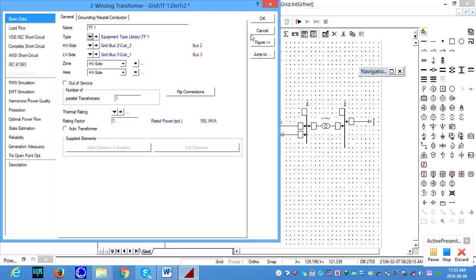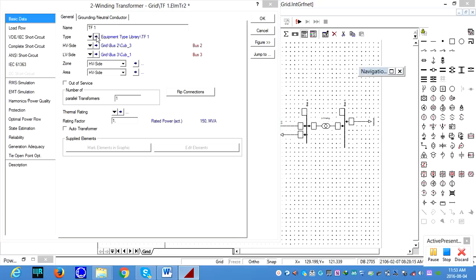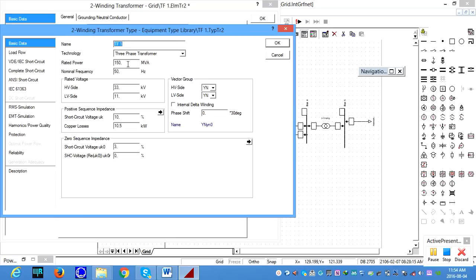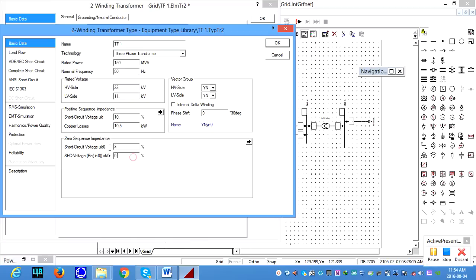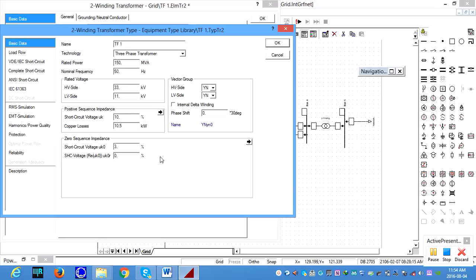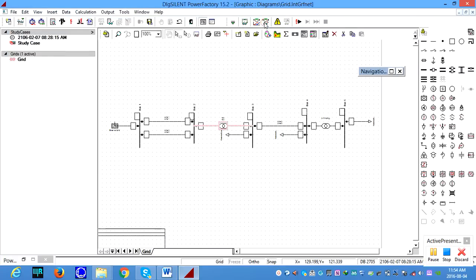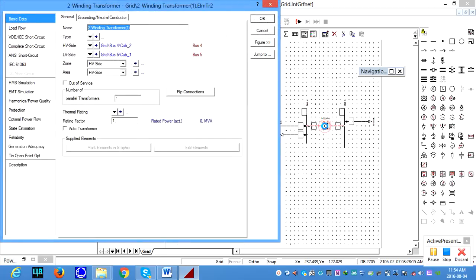Okay. That's correct. If you want to double click to check, you can make sure the transformer rating is 150 MVA. HV side is 33, LV side is 11, and your short circuit voltage is 10, your copper loss is 10.5. And the zero sequence impedance value, if we are trying to implement or test the scenarios for the ground faults, okay, then the zero sequence impedance must be taken into account. For default, I leave it for this case. Okay. Next, we go for transformer 2.